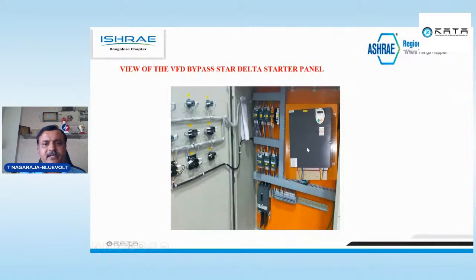Then the EMC plate. Generally, what will happen? People will not use the EMC filter, this plate. Along with the VFD, any make of the VFD, they will give one EMC plate. So please fix it to the VFD. That means your EMC interference will be avoided. This is also with MCCB as an incomer and contactor.